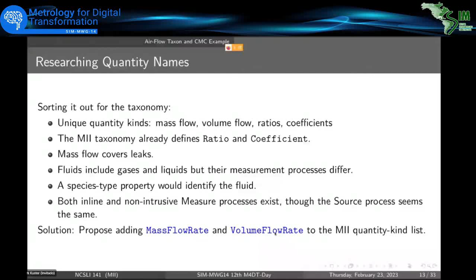After looking at all that, we would propose adding two taxons to cover our particular needs in the laboratory: mass flow rate and volume flow rate. While doing so, we might come up with a hierarchy, a partial taxonomy, to cover this measurement area, so we can source and measure these quantities. We have mass and volume flow for either gas or liquid, inline or non-intrusive meters, and you can see how we qualify these taxons further and further.